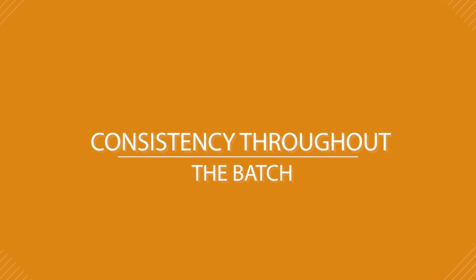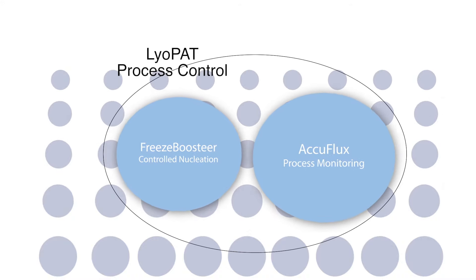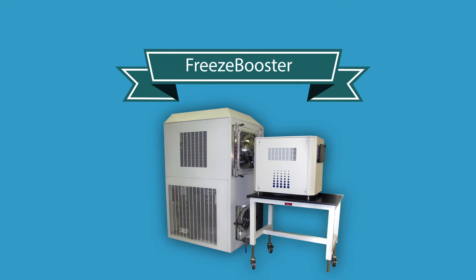But wait, there's more! We have mastered the art of nucleating all the vials at the same time, same temperature, same rate — giving you consistency throughout the batch and within the vial. LyoPAT combined with Freeze Booster controlled nucleation technology produces a higher quality product and consistency.